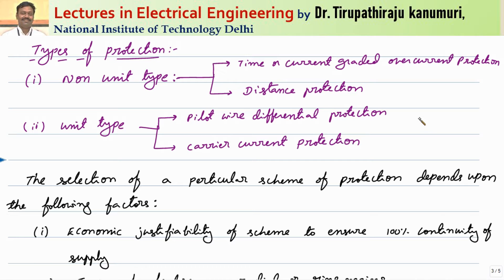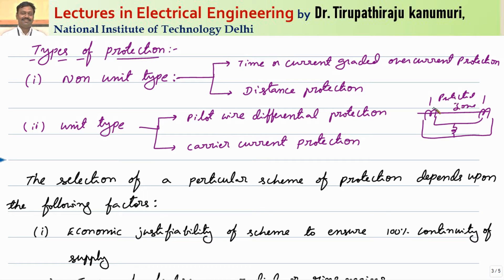In differential protection of a line, a CT is placed at each end point. The difference between the two points is used for protection — this is the protected zone. The relay will respond only to faults that happen within this particular zone, which is why it is called a unit. There are two types: pilot wire differential protection and carrier current differential protection. For non-unit type, protection is not limited to a particular zone and can extend over longer distances. These include time or current graded overcurrent protection and distance protection.